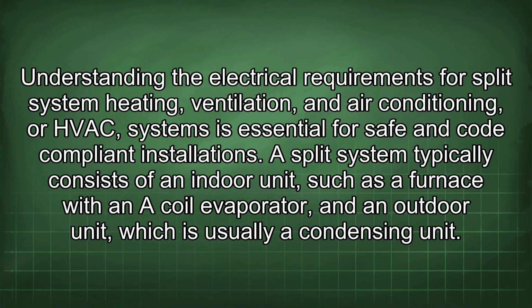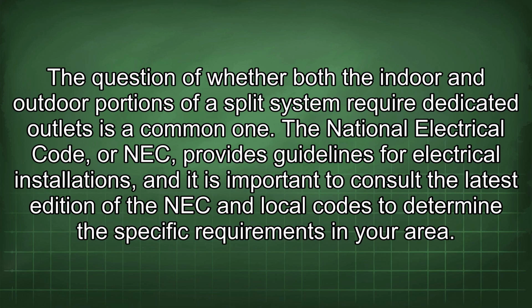Understanding the electrical requirements for split-system heating, ventilation, and air conditioning, or HVAC, systems is essential for safe and code-compliant installations. A split system typically consists of an indoor unit, such as a furnace with an A coil evaporator, and an outdoor unit, which is usually a condensing unit. The question of whether both the indoor and outdoor portions of a split system require dedicated outlets is a common one. The National Electrical Code, or NEC, provides guidelines for electrical installations, and it is important to consult the latest edition of the NEC and local codes to determine the specific requirements in your area.